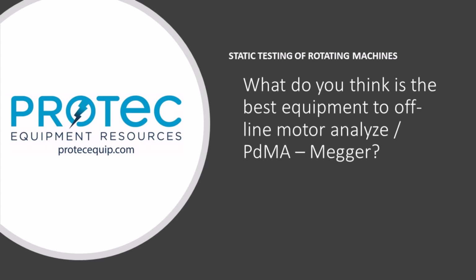And then you have the PDMA, which makes both static offline testing equipment as well as dynamic online testing equipment. Both manufacturers, I really can't say a negative. Quality of product is very good. In the static world, you'll find a lot of similarities between the PDMA and the Megger Baker product offerings. They'll do the insulation resistance, they'll do the winding resistance, they'll do the ramp test, they'll do the step voltage test. The big difference in the brands is the PDMA, unless they've changed something in their product portfolio, they do not offer the surge test, either the surge comparison or the pulse-to-pulse surge test.